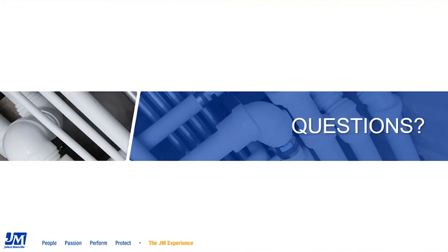Excellent, thank you. John, can you define K-value for us? The short definition is it's thermal conductivity, and it's a measurement of the heat flow that's going through 1 inch of insulation that's 1 square foot in area, and it's enough heat to raise the temperature 1 degree Fahrenheit.